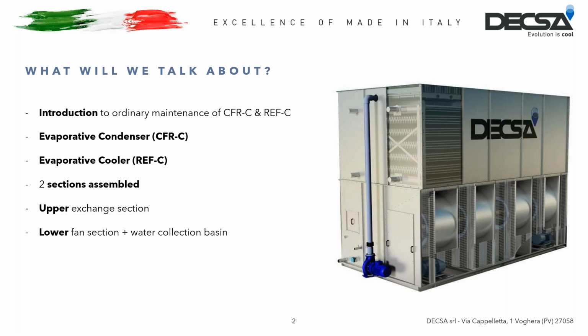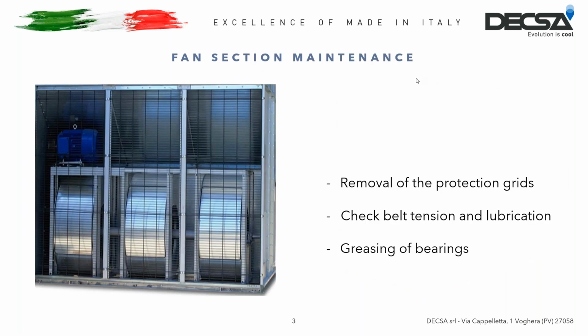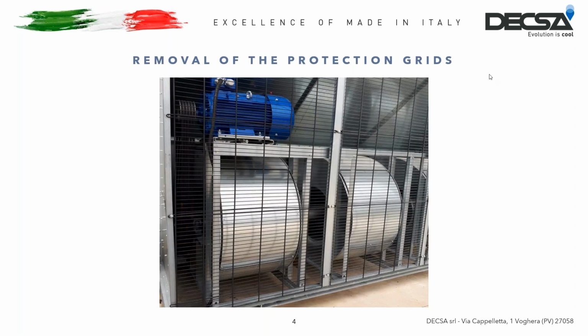Let's start by checking the centrifugal transmission. Obviously, the work must be done by a qualified technician and the motor must be switched off and the area must be closed following all the safety rules. To assess it, you need to remove the protection grids, unscrewing the bolts that fit them to the unit. The size of the bolts may change according to the age of the unit. However, we are talking about a 10 or 13 wrench or a screwdriver with a socket of this size.